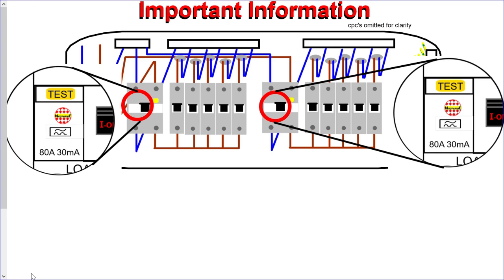important information we need before we start. Should be looking at your RCDs. You'll see here we've got a dual load RCD, split load RCD, dual RCD board. We've got an 80 amp, 30 milliamp RCD, but you'll see both of them, again, same ratings, both of them are type A RCDs. Okay, so this information is important.